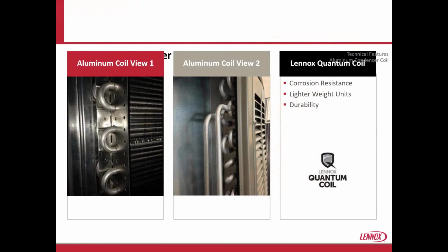The outdoor coils on all of our equipment, we're converting to quantum aluminum coils. One thing to note about this is on the tube sheets itself, we use aluminum end sheets, so we don't have dissimilar metals. That's one thing I think to note on our products there. It's not going to have galvanized or something like that.